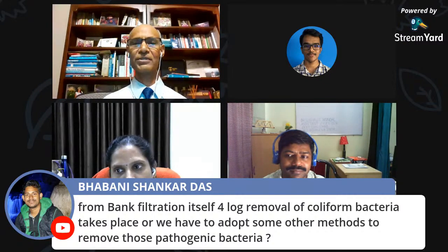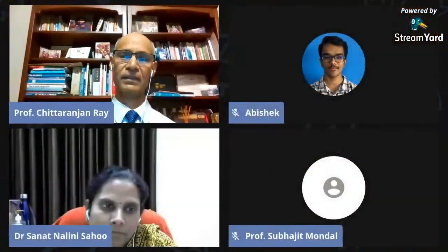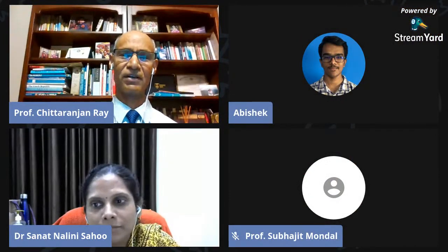That was the case of what happened in Milwaukee, Wisconsin in 1993 that killed 120 people and sickened about 400,000 people, because there was a breakthrough of these Cryptosporidium through the sand filtration system. So the four log removal really occurs if you have a good working filter and the backwash is controlled. During the backwash time, there is some possibility of some entrapped spores of Cryptosporidium or Giardia passing through. But you have to have a proper mechanism to remove those. But for bacteria and viruses, whether they are pathogenic or non-pathogenic, you can kill them with chlorine contact. And hopefully it's clear, but you can ask again if you are not clear.